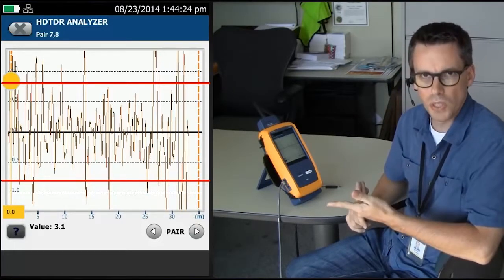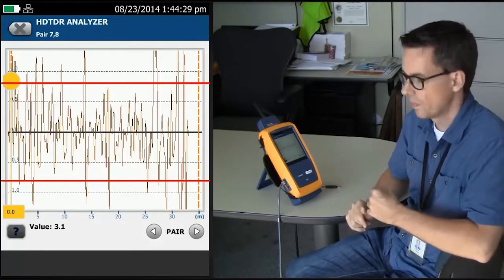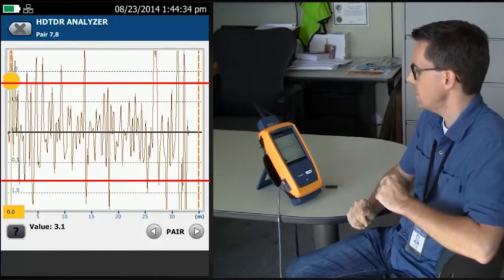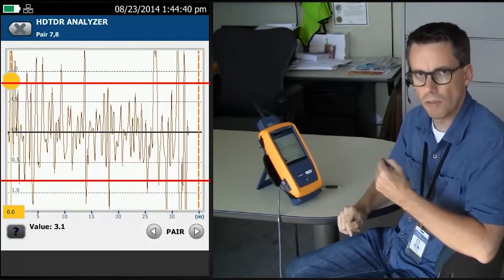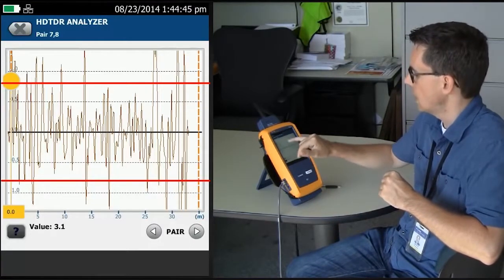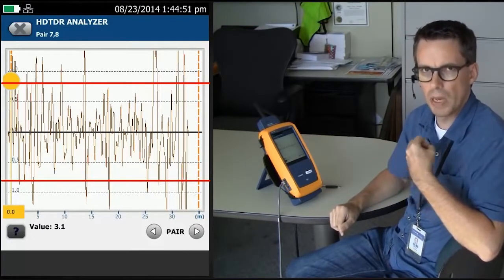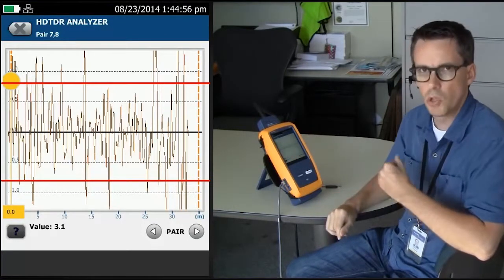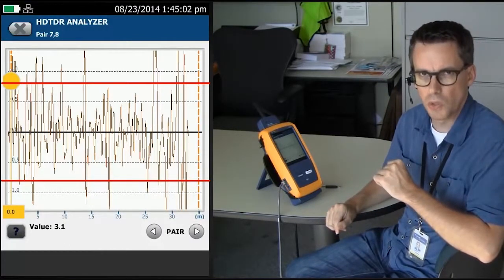And of course, whose fault is it? Is this badly made cable or is this cable that got damaged during the installation? I make a point of not saying that. However, when you look at this trace here, you'll notice that there are segments of the cable which are far less than 0.8%, but there are other parts of the cable which exceed it by a noticeable amount. If the cable was made badly, you'd expect it to look bad all the way down. When you only see certain segments of the cable, you could be forgiven for suggesting that maybe this was something done during the installation.